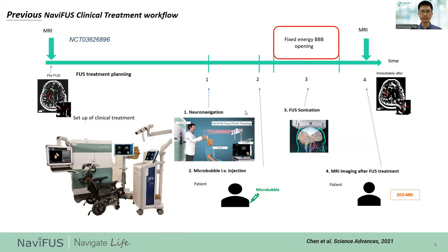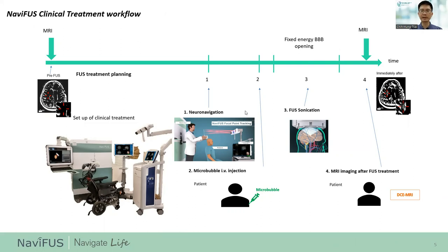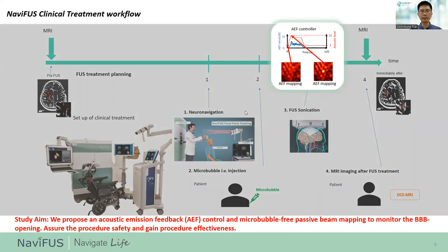Because the NaviFUS transducer phased array design allows it to be operated in dual transmit and receive mode, we can apply multiple acoustic emission signals to develop an AEF controller. During treatment, there is an opportunity not only to control the emission level to secure the exposure through the AEF controller, but also to feed back the focal beam mapping to confirm the pressure deposited in the brain. In this study, we proposed an AEF controller and a microbubble-free AEF passive beam mapping to monitor BBB opening, assure procedure safety, and gain procedure effectiveness.